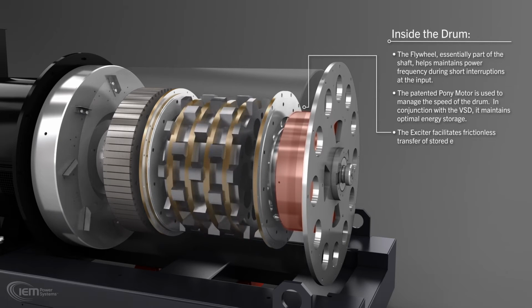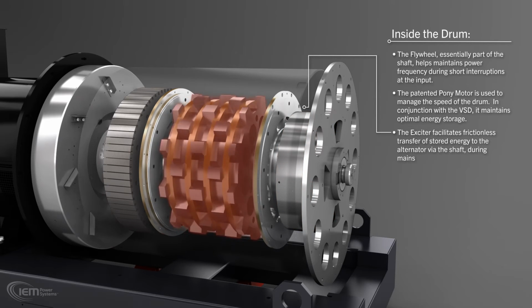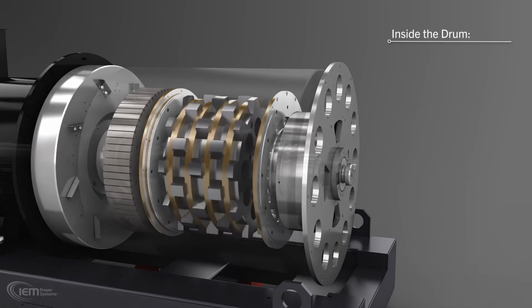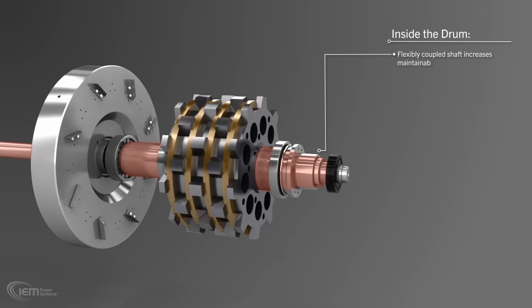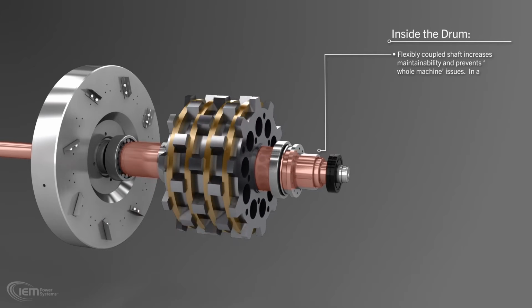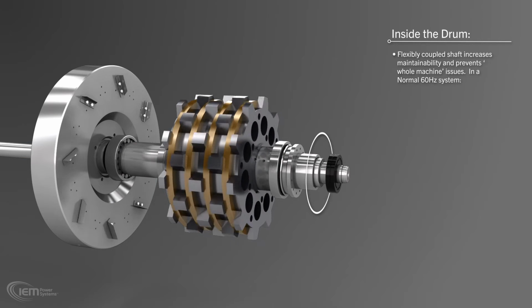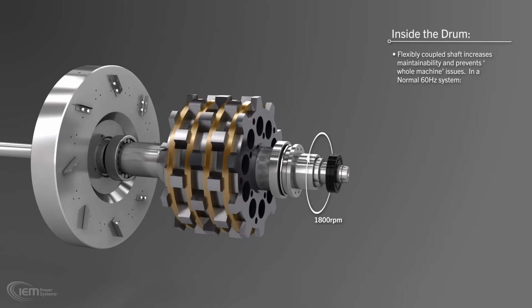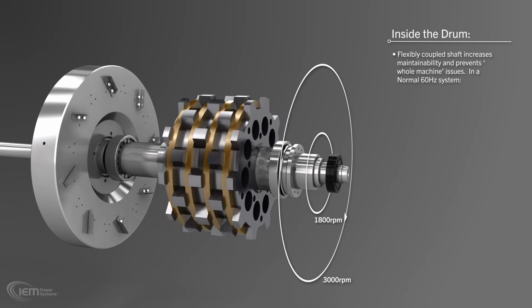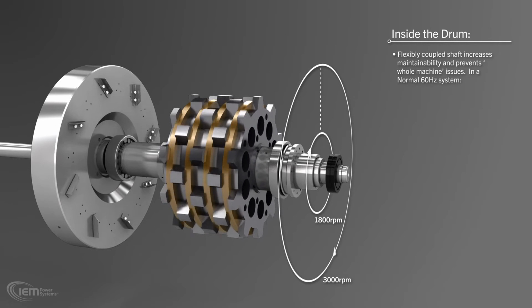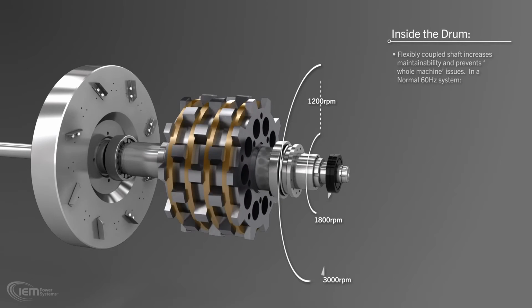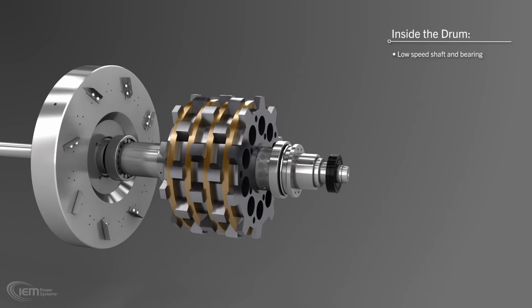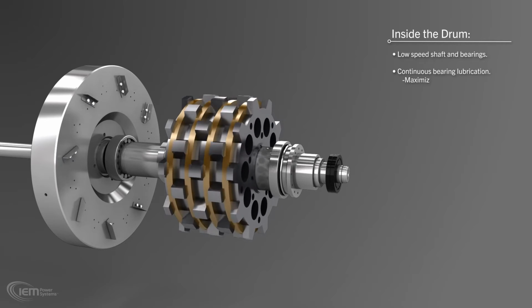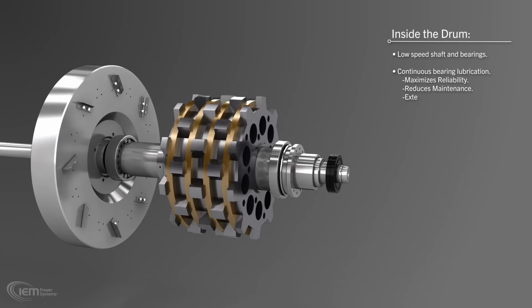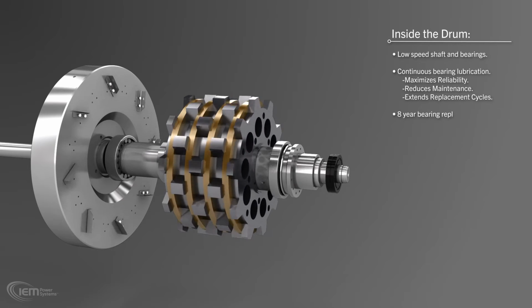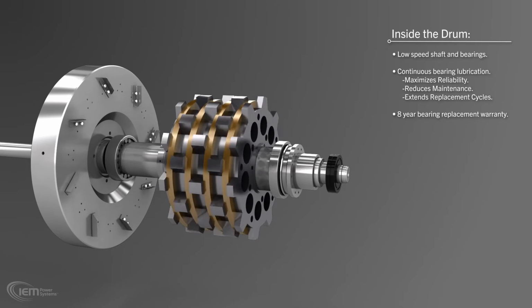The exciter facilitates the frictionless transfer of stored energy to the shaft during interruptions to mains power. The coupled shaft increases maintainability and prevents whole machine issues. In normal operation, in a 60 Hz system, the shaft turns at 1800 RPM. With the maximum speed of the storage drum being 3000 RPM, the maximum relative speed is only 1200 RPM, low for a rotary UPS. The Rotoblock's low-speed shaft and bearings, combined with continuous bearing lubrication, maximizes reliability, reduces maintenance, and extends replacement cycles. IEM Power Systems provides a full 8-year bearing replacement warranty.